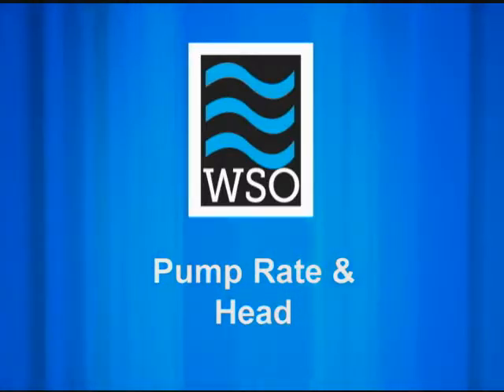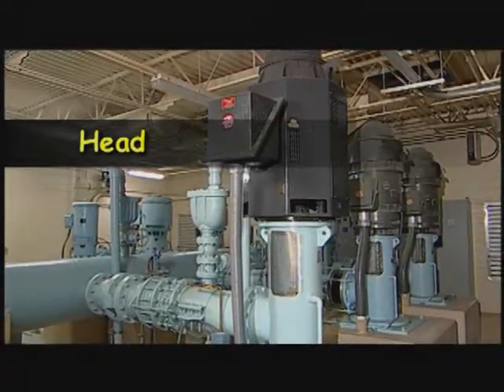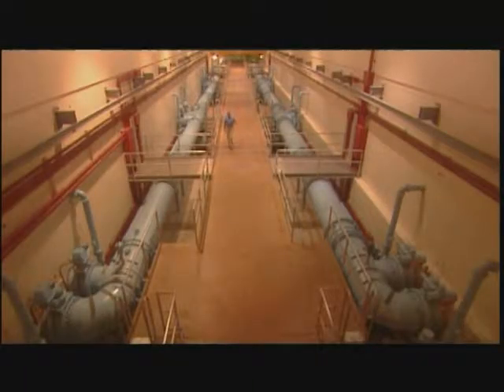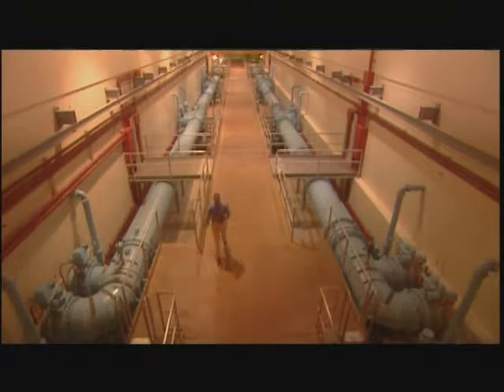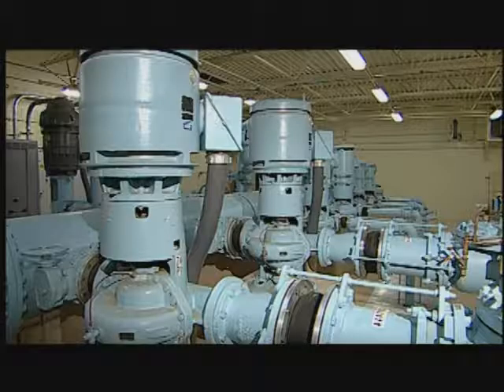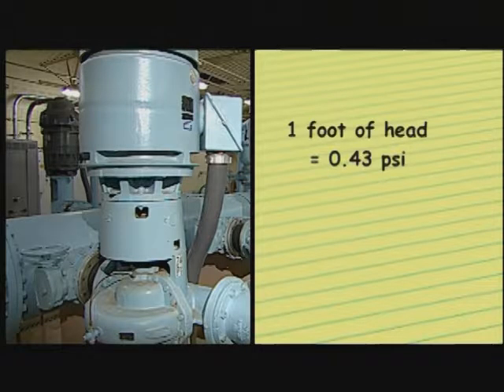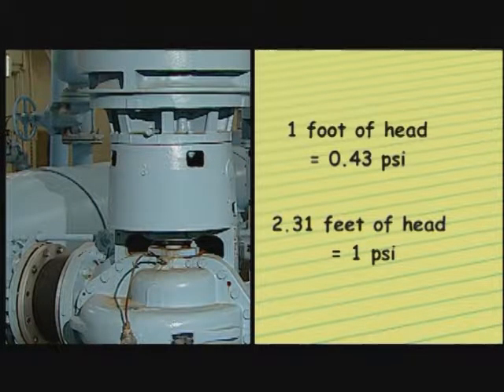Head is a measurement of the energy possessed by the water at any particular location in the water system. Head is used to calculate the hydraulic forces acting in a pipeline and to determine a pump's capacity to overcome or pump against these forces. One foot of head is equal to 0.43 PSI, or 2.31 feet of head equals 1 PSI. Make sure you know these conversion factors, as water operators often need to convert back and forth between PSI and head.